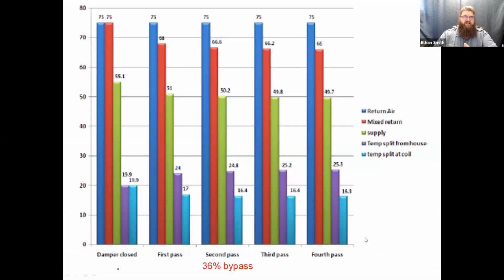So this is a 3-ton system. I believe this is in cooling mode. Yes, it is. We have our return air in blue, our mixed return air in red, our supply temperature in green, and our temperature split at the house and our temperature split at the coil in purple and light blue respectively. Over here on the left, we have the system operating with my bypass damper closed.